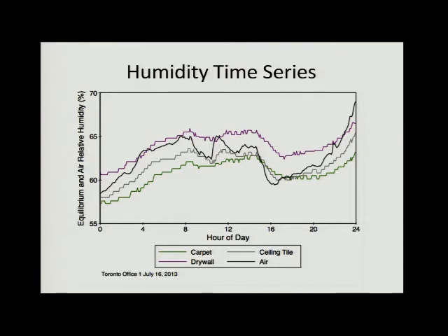So those of you who know me know I like to make measurements for long periods of time in buildings, years, if I can get away with it. And so this is a measurement. This is in an office in Toronto. This is just one day, to not be overwhelming here. The black trace in the middle there is the air relative humidity, and the other colors are 3 different building materials, the equilibrium relative humidity above those materials.